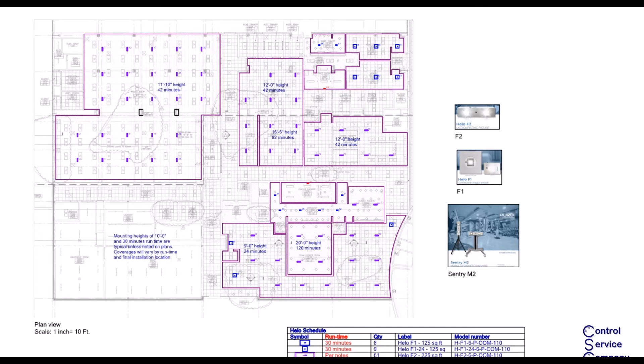A little further down we talk about run times. Remember I mentioned heights - I'll zoom into this area with a 12-foot ceiling, a 16.5-foot ceiling, and another 12-foot ceiling. The ones without height listed default to 10 feet, which runs a 30-minute cycle. So by default, spaces that are outlined but not called out with different heights run the lighting for 30 minutes a day, which is recommended for sanitation and disinfecting. The other spaces: 12 foot runs 42 minutes, 16 foot runs 82 minutes, and so on. You can see we control these individual spaces uniquely to make sure we're effectively disinfecting.